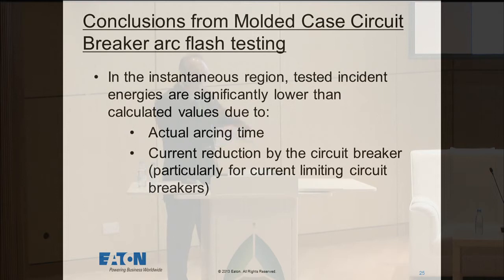That happens very quickly, and it also makes another arc that's in series with the accident that's occurring downstream. When the arc flash is occurring down there because someone put a wrench on it, and you start opening up the circuit breaker, this is all happening in milliseconds. It's limiting the current already to what happens downstream. So we know that circuit breakers are very good at current limitation, and that helps you for arc flash.